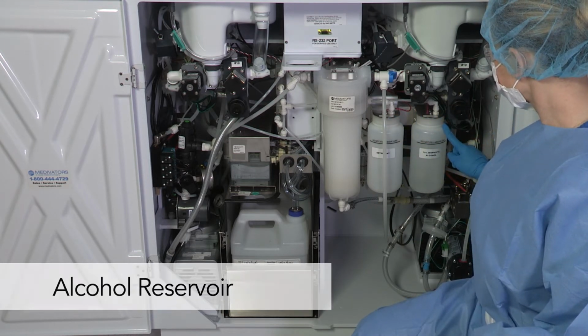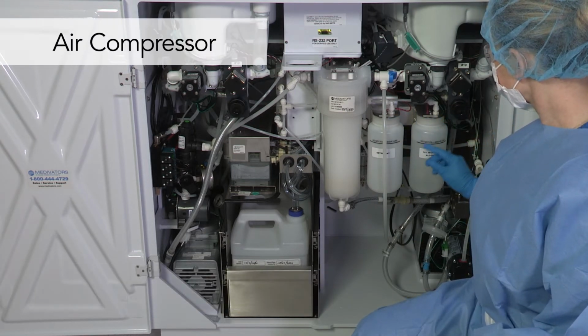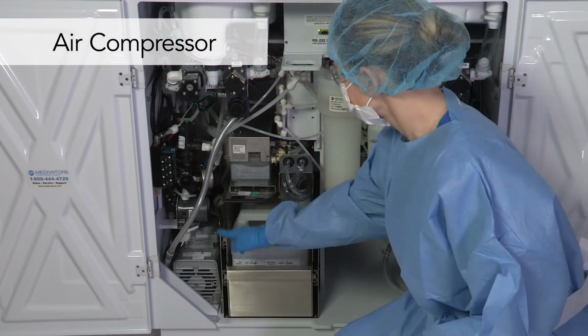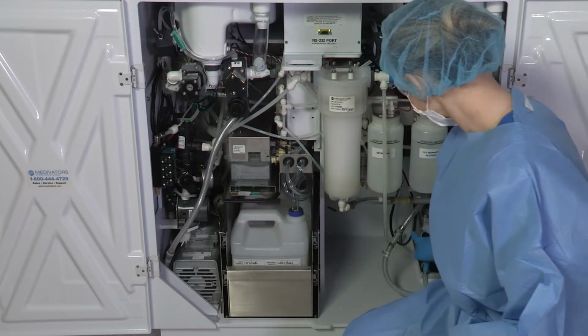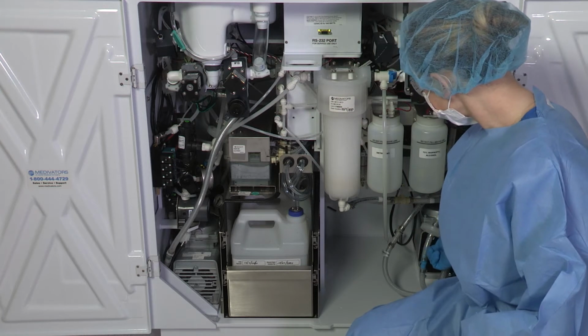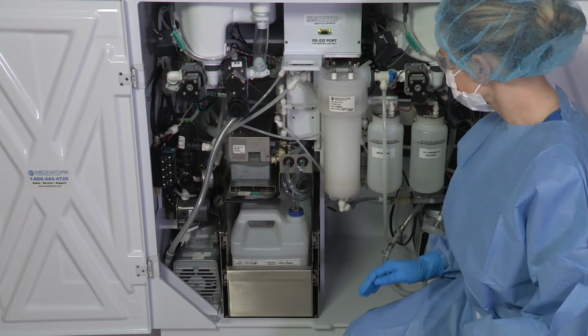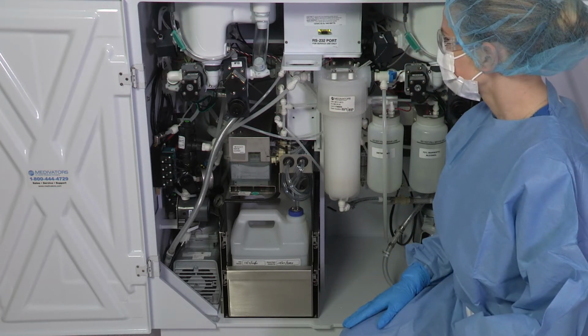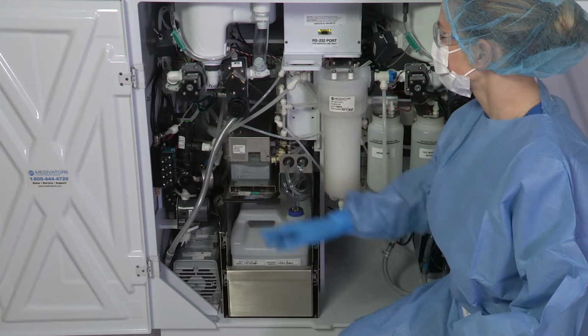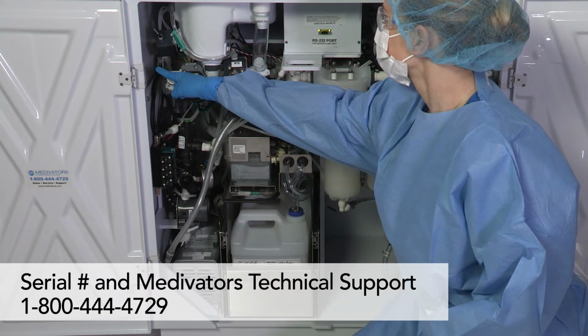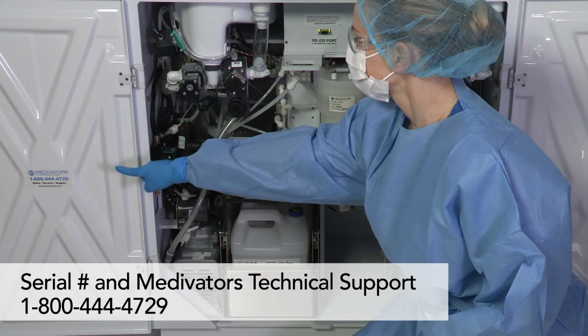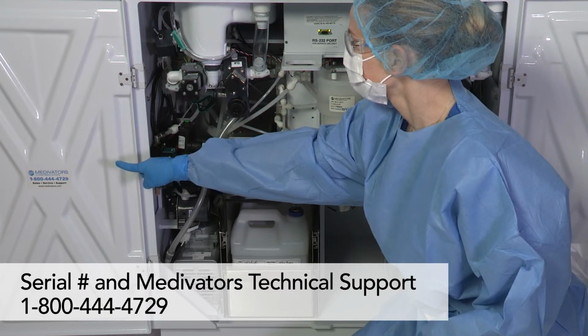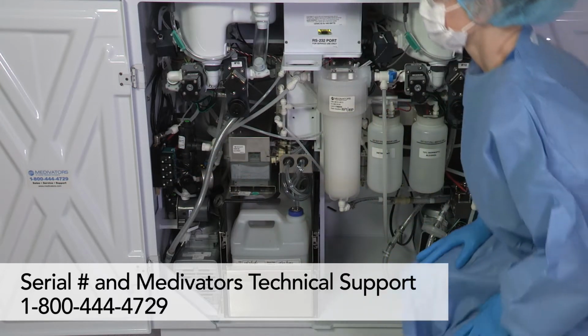The DSD EDGE Reprocessor is equipped with a built-in compressed air system with 2 0.2 micron air filters, 1 for each basin, to deliver high-purity air to assist in removing residual water from the endoscope channels. The label containing the serial number is located on the left side wall. Medivator's 1-800 number is located on the inside of the left door.